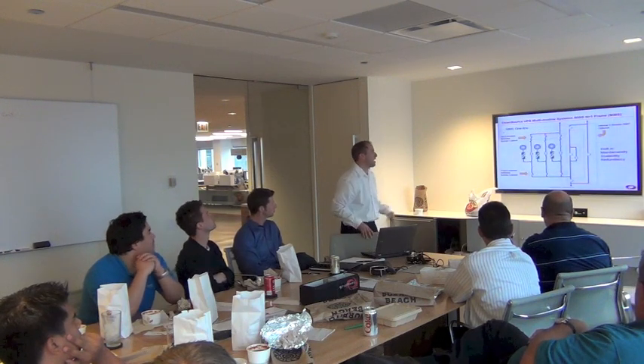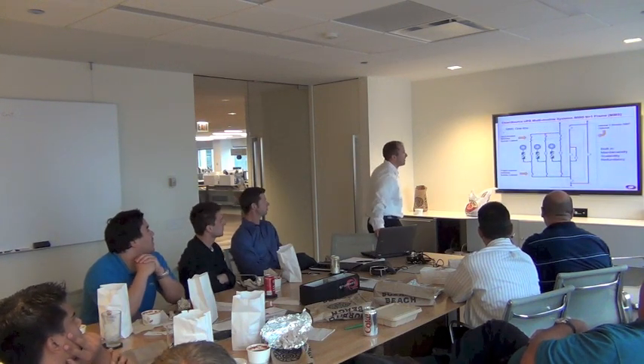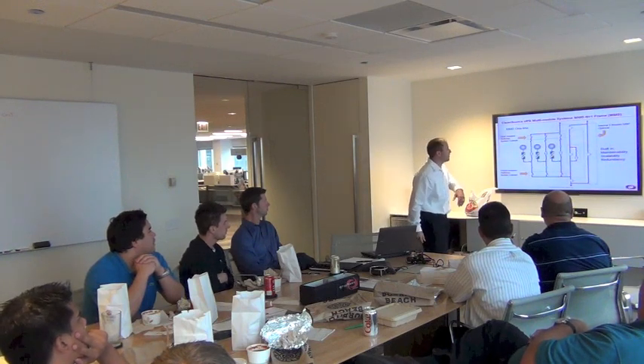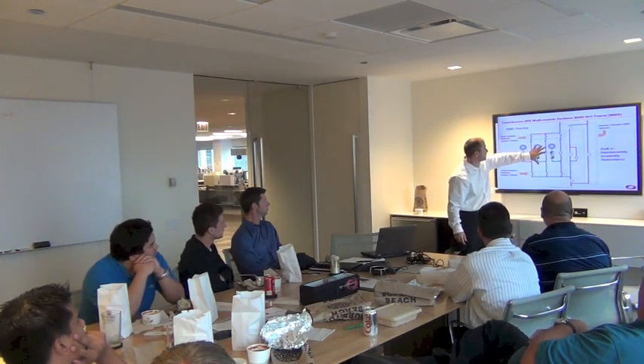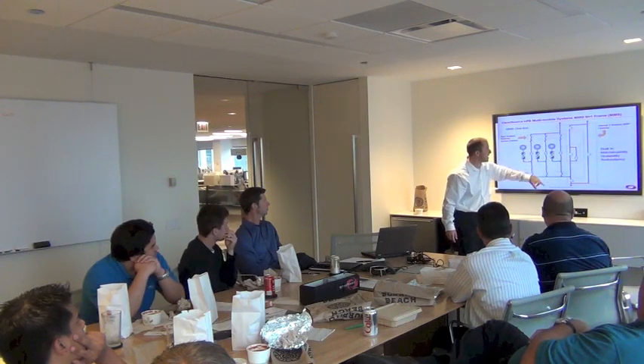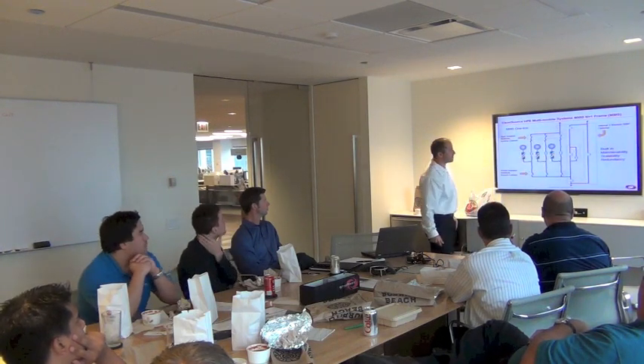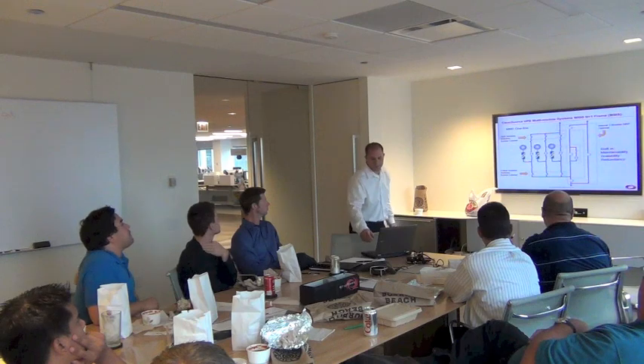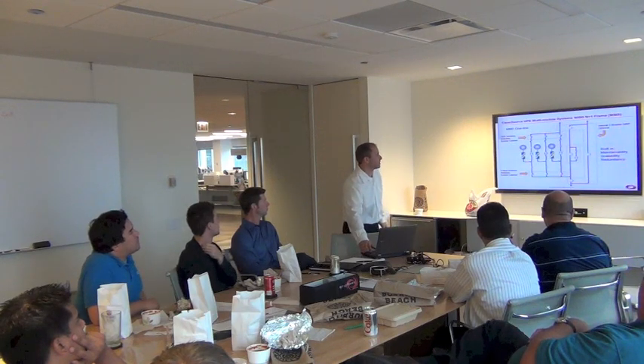So this is just a high-level one line of a 900 kVA or a 600 N+1 kVA UPS. You can see each of your flywheel cabinets houses most of the critical components. You have disconnect switches in the systems cabinet, and then you have your bypass in the systems cabinet as well. And there's an option there for a 3-breaker maintenance bypass with what we refer to as the G frame, which is up to 600 kVA.